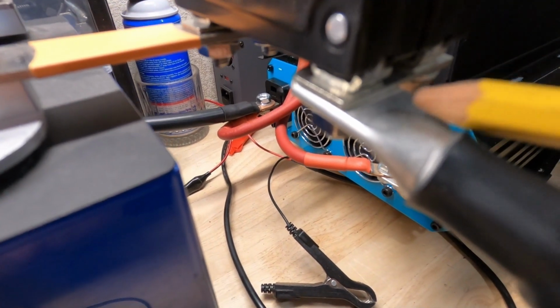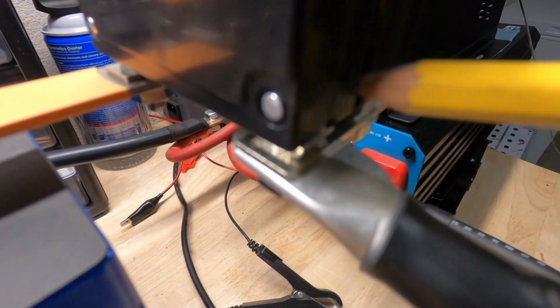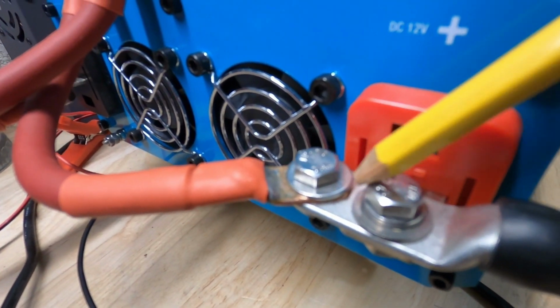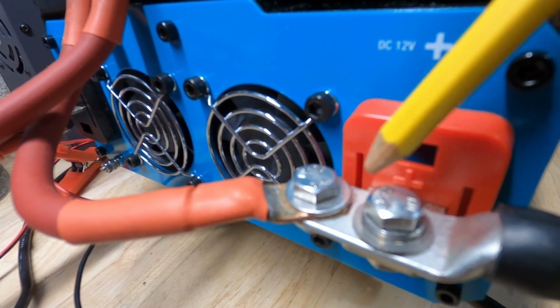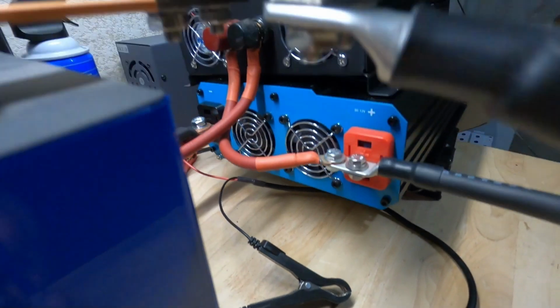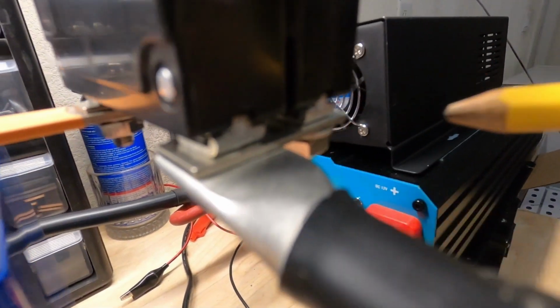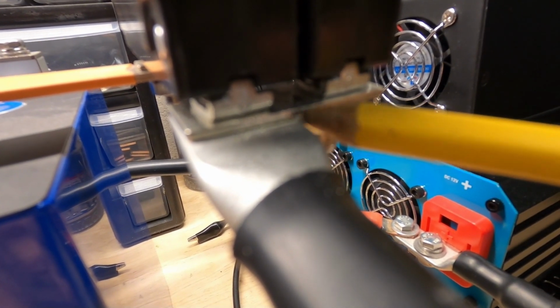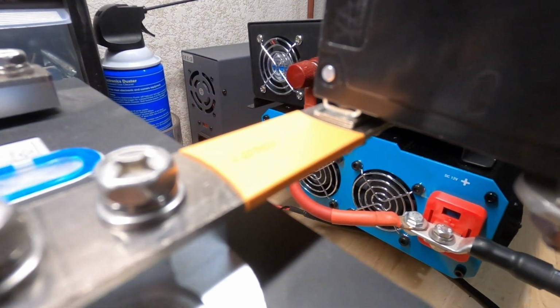On this side, they used a single hole lug, and over here on the BMS side, this would normally be on the BMS, it has an actual double hole lug. And this is something I complained about when I did the review video, is why they didn't use a double hole stud or lug on both sides of this cable and just span the 2 contacts and get rid of this little piece in the middle, because if you notice, it's quite thin and it's basically obstructing the current flow. There's no need for this. I mean, they have it here obviously so it can span the 2 poles and act as a bridge, but totally not needed if they used a double hole lug, and definitely not needed on this side.